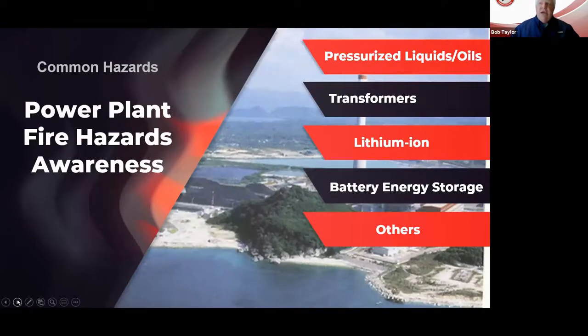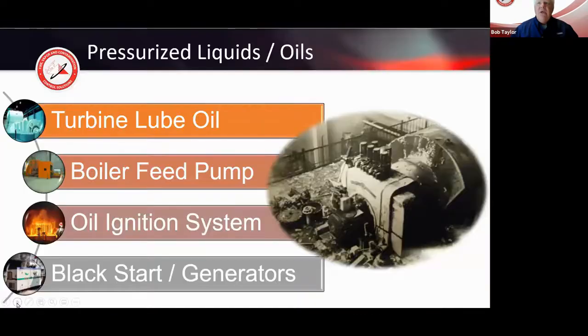So let's take a journey down the area of looking at pressurized liquids and the oils and the transformers and lithium ion and some of those areas as we continue. Pressurized liquids and oils. We know that some of the common hazards are the turbine lube oil systems. Those are critical areas, and often those areas continue to pressurize and continue to flow atomized liquids until the equipment comes to complete rest, which is not normally very quickly.